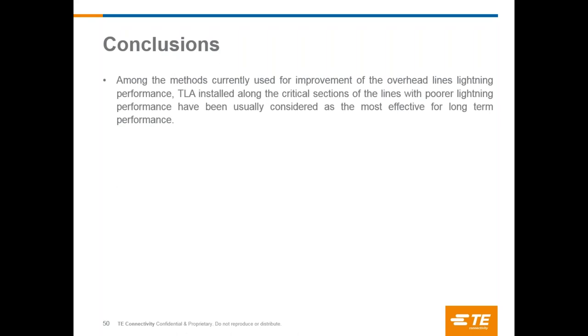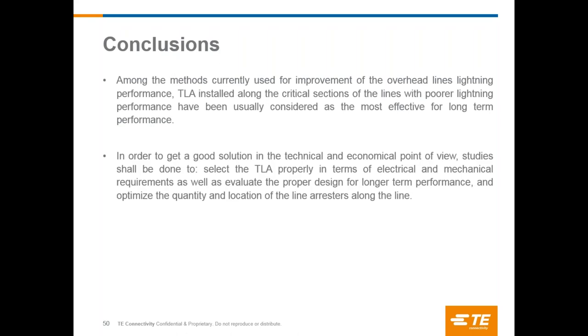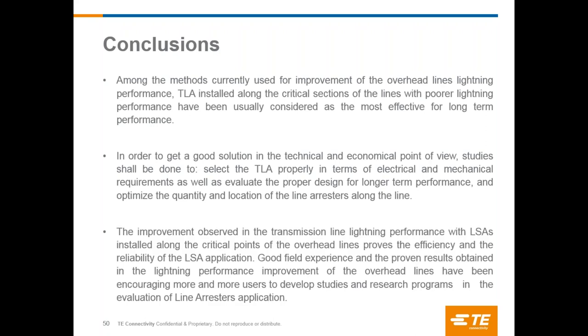Talking specifically about line surge arrester application, in order to get a good solution from the techno-economic standpoint, studies shall be done to select the TLA properly in terms of electrical and mechanical requirements, as well as evaluate the proper design for long-term performance and optimize the quantity and the location of the line arresters along the line.